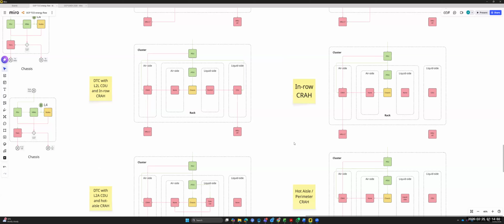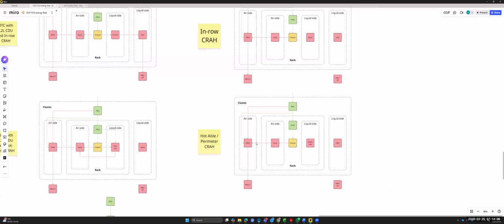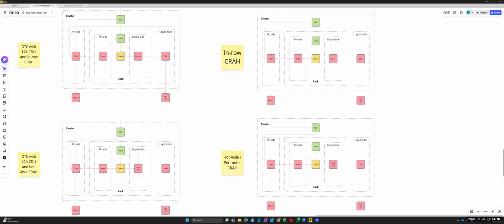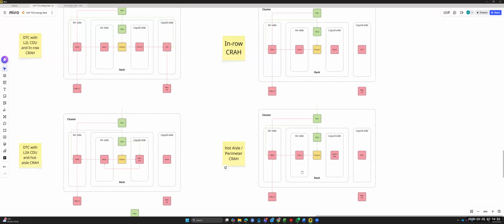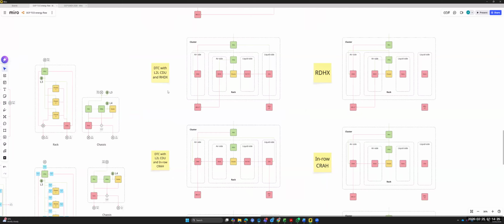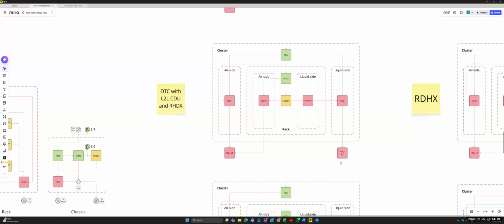It can handle the very basic situation where all the heat goes to a CRAH and is cooled via the low temperature heat rejection unit. But you can also build out to very complicated configurations - for example, where you have direct chip cooling in the chassis, cooled to the high temperature heat rejection unit, and the remaining heat on the air side is cooled by a rear door heat exchanger that itself is liquid cooled by the low temperature heat rejection unit, with the remaining heat loss on the air side in the data room being soaked up by a CRAH in the perimeter.